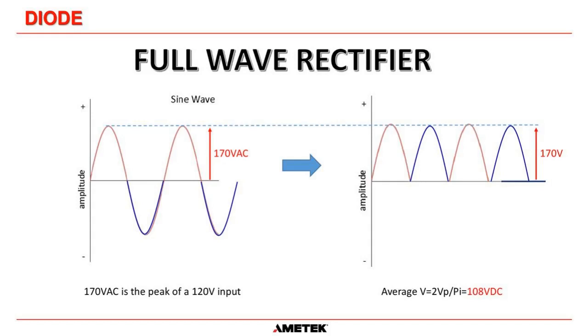So when we make DC, we have to make that DC stay at 135 volts no matter what. And you say, well, that should be easy - just make the input to the rectifier bridge equivalent to whatever the output is to make it 135 volts. Well, that's not going to work because we rely on the grid power from whichever plant our UPS is connected into supply power to the rectifier.